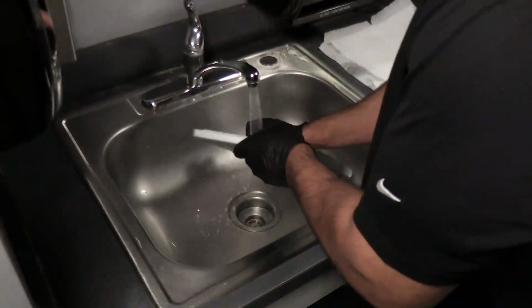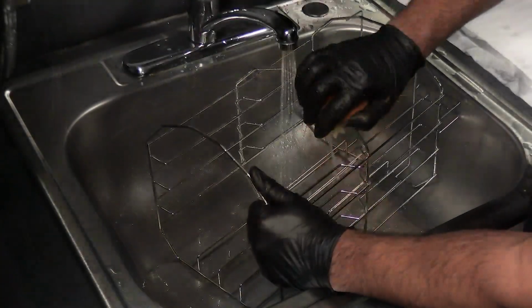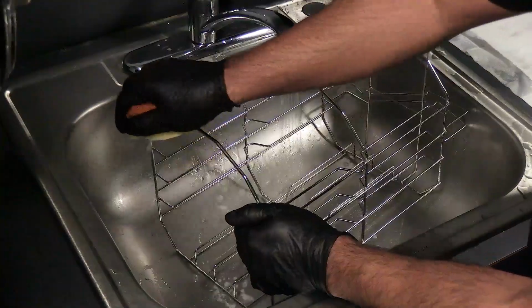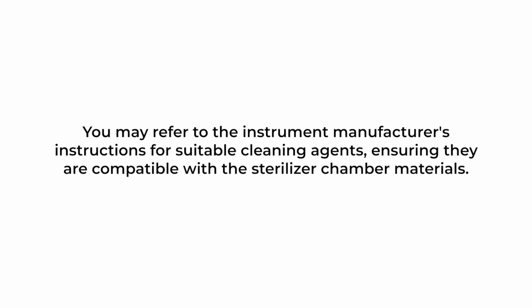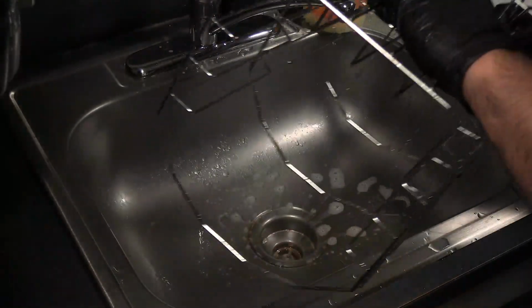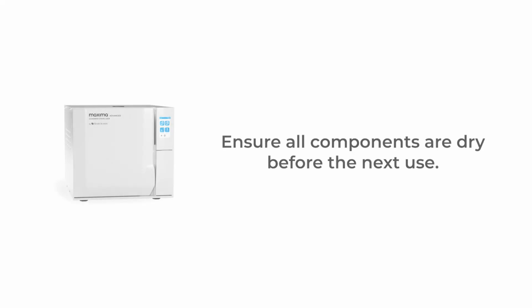Rinse the filters with tap water to remove any debris. Clean the chamber, trays, and the rack with a slightly damp sponge and a mild detergent solution. You may refer to the instrument manufacturer's instructions for suitable cleaning agents, ensuring they are compatible with the sterilizer chamber materials. Rinse the chamber, trays, and the rack thoroughly with clean water to remove all traces of detergent. Insert the filters back into their original position, screwing them in until snug. Ensure all components are dry before the next use.